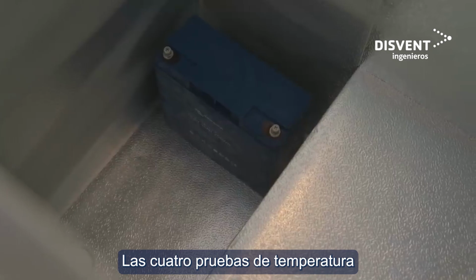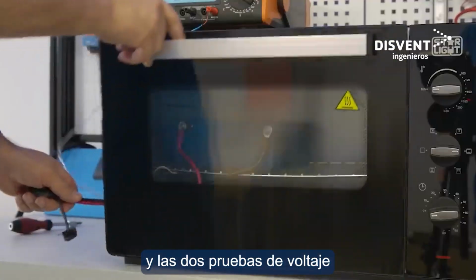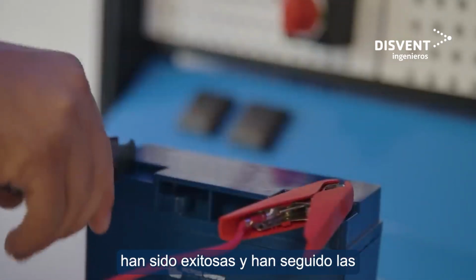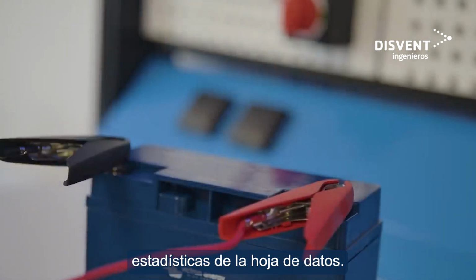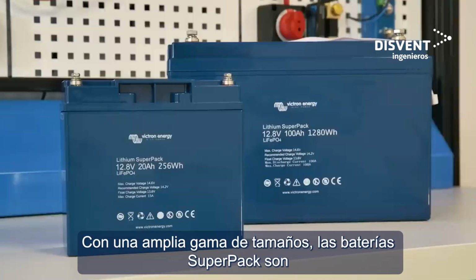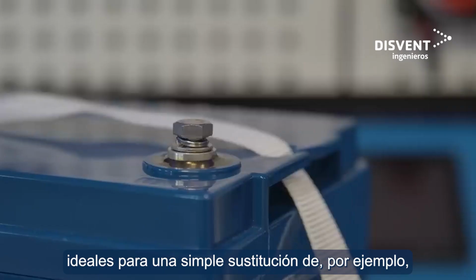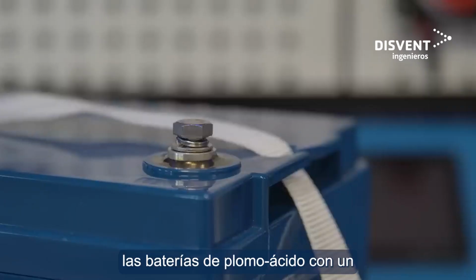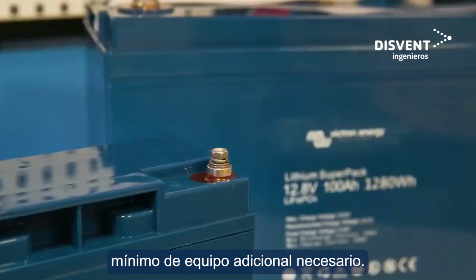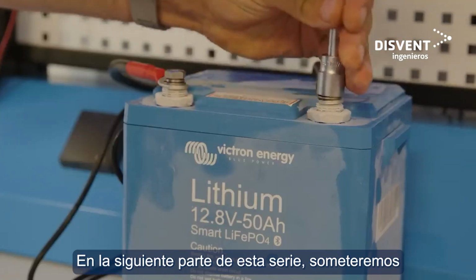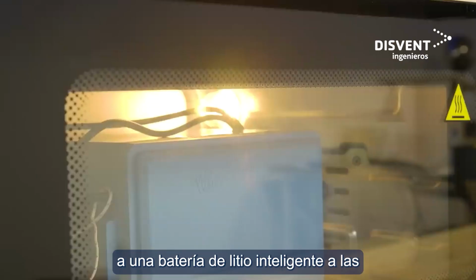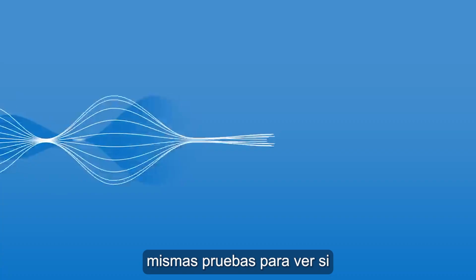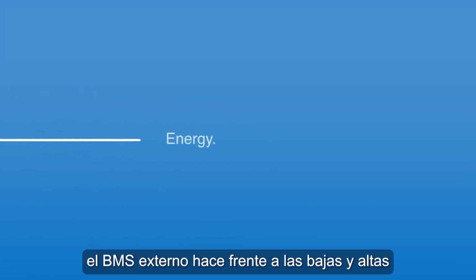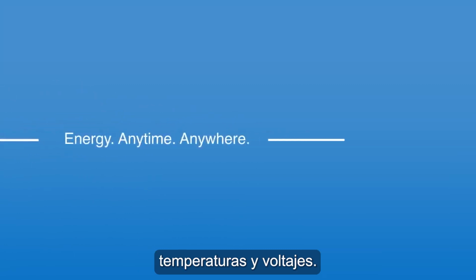All 4 temperature tests and both voltage tests have been successful and followed the datasheet statistics. With a wide range of sizes, the SuperPack batteries are ideal for a simple replacement of, say, lead acid batteries with minimum additional equipment needed. In the next part of this series, we put a lithium smart battery through the same tests to see if the external BMS copes with the low and high temperatures and voltages.